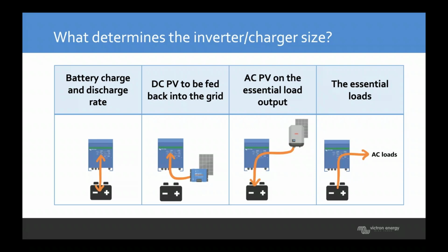Another factor is how big the AC PV is on the essential output load. If you know you want a big AC PV inverter, you have to have a big MultiPlus to accommodate it. And then finally, the size of the loads, how big the loads are that you want to run.